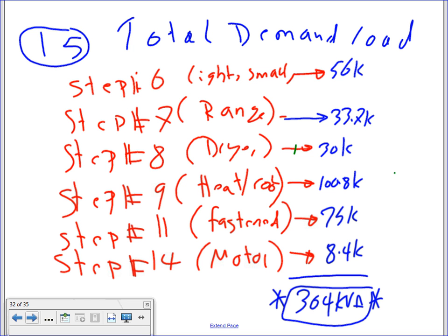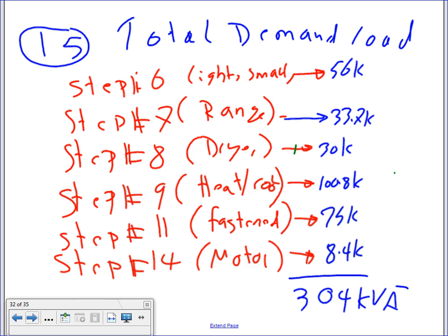Any comments, guys? Any questions? Just add them up. So you can see we add the lights and small appliances, range, dryer, heat, cool, fastened in place, motors. Add them all up. 304, yep. Looks like a 6, isn't it? I'll give you 304. Let's write it down one time here. 304 kVA. Why can't I get the 0 to close here? It's hard to write with that. You lose your synchronization after a while with that, man. That's a 0. Okay. Now, please leave room here because I'm going to do the neutral on the side.